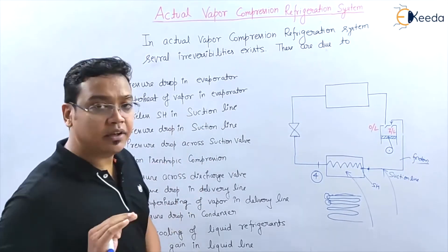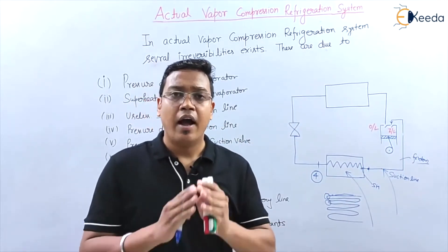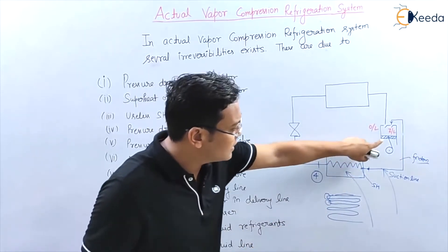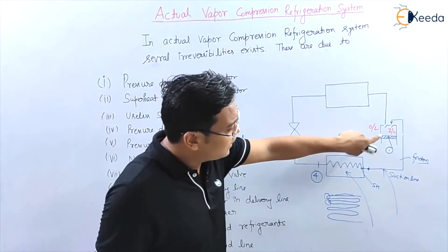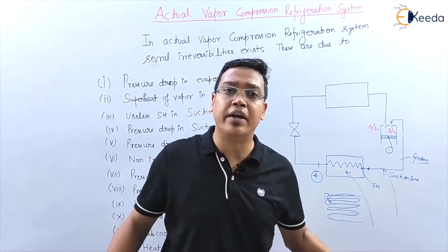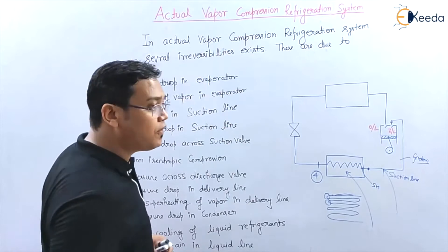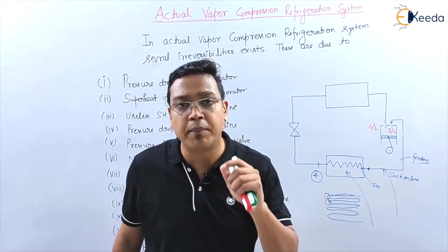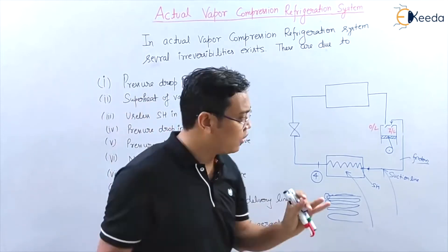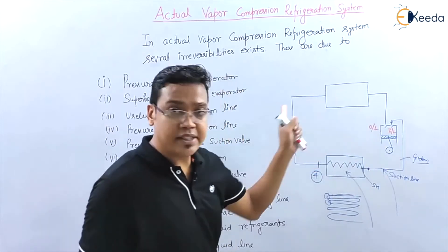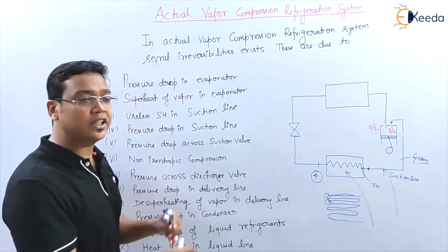The next irreversibility is non-isentropic compression. In an ideal cycle, compression takes place isentropically, but because of internal irreversibilities in the reciprocating compressor, the actual compression process does not follow an isentropic or adiabatic process. After understanding all these points, I will draw the T-S and P-H diagrams for the actual vapor compression refrigeration system.